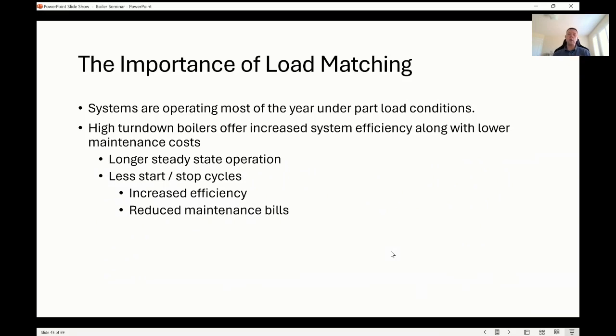I call it almost like highway driving versus city driving. So a high turn down ratio boiler will have less start-stop cycles. Any boiler and most machines will be most efficient at steady state operation. They don't want to start and stop. It's like your car. If you drive that same car in the city and you drive it on the highway, you're going to get much more fuel efficiency on the highway than you are starting and stopping in the city. It's the exact same thing with the boiler.